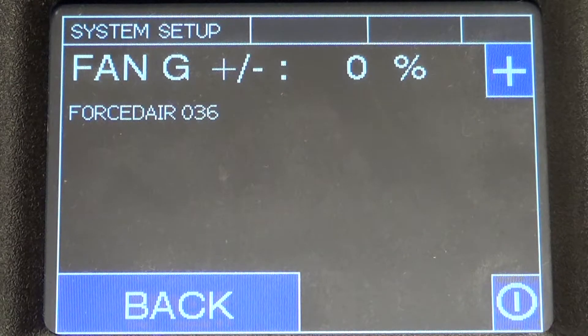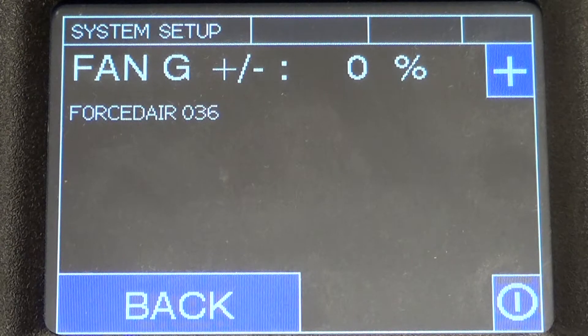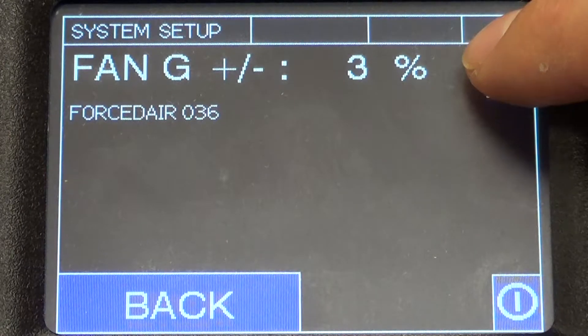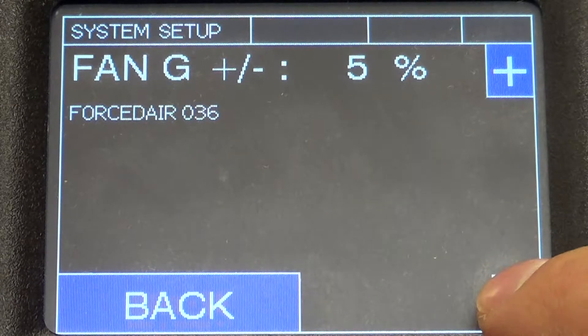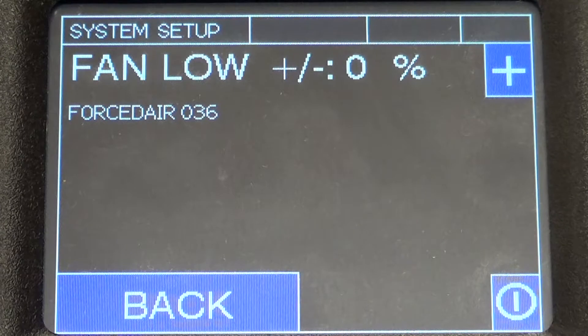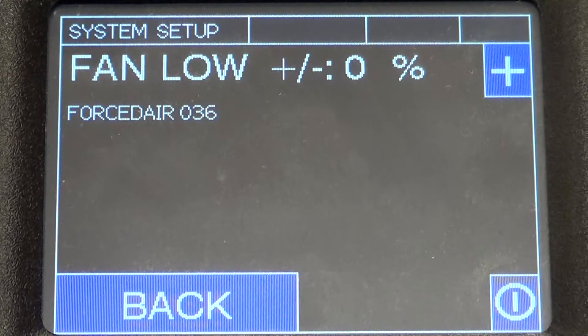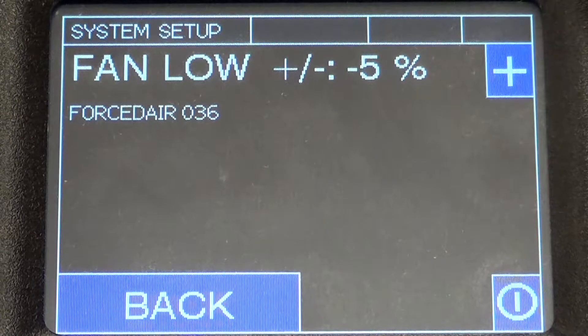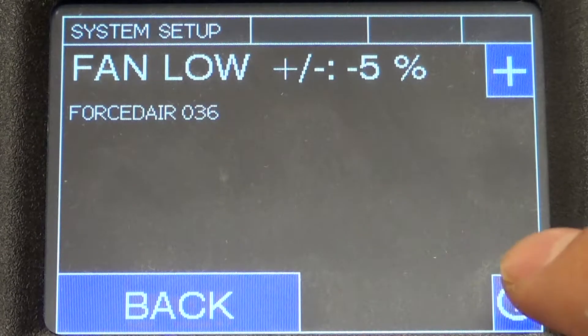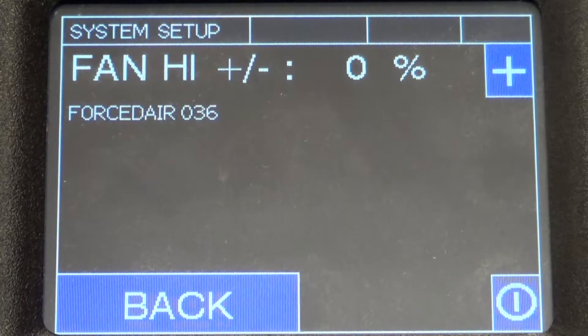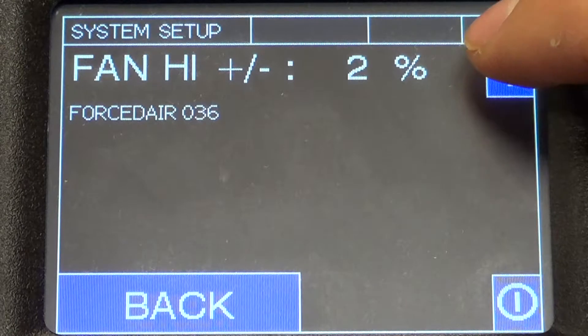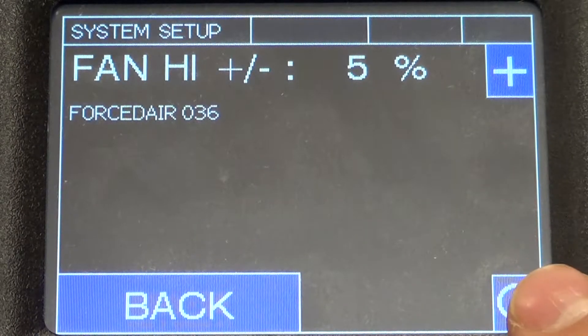The next three screens allow for control of the fan for plus or minus five percent of the air flow. Fan G is the setting the fan will run at in a call for fan only — when there's a G call, maybe you want more airflow, so plus five percent. Fan Low is the fan speed when the compressor is in low stage, so maybe minus five percent. Fan High is the speed when the compressor is in full stage — we'll go plus five percent for that one.